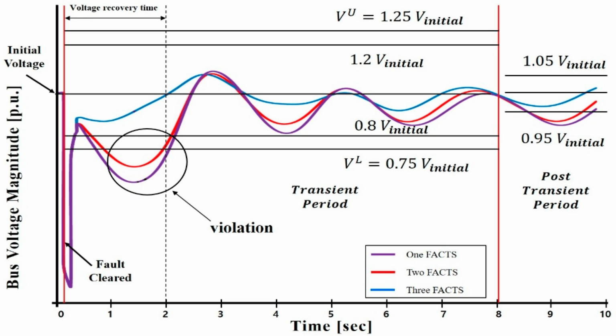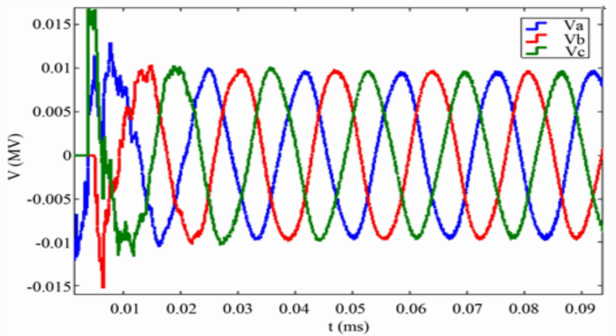The degree of a system's voltage stability, or the proximity to voltage instability, is strongly influenced by system conditions and its characteristics, such as generation system characteristics, in particular excitation systems, load characteristics, reactive power compensation devices characteristics, voltage control devices, presence of under-load tap-changing (ULTC) transformers, etc.